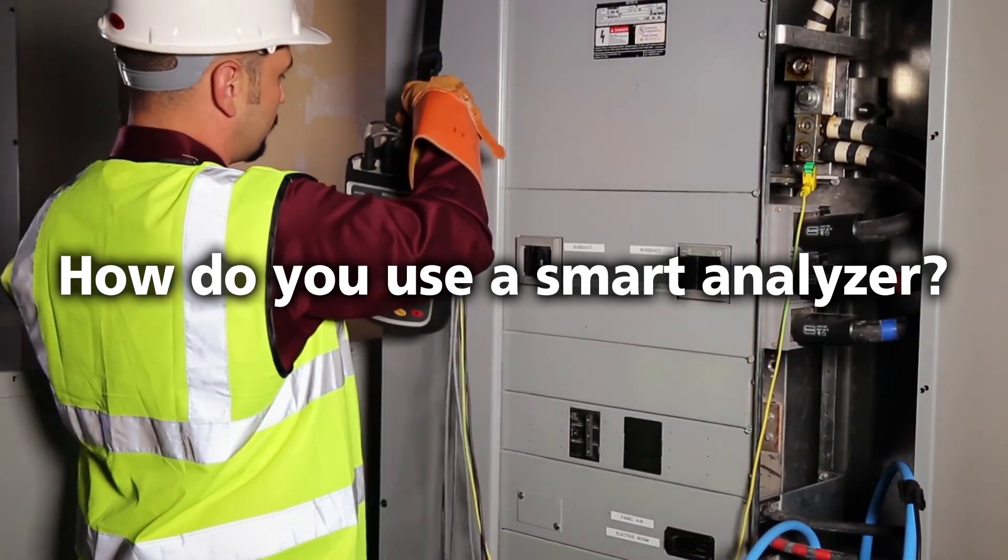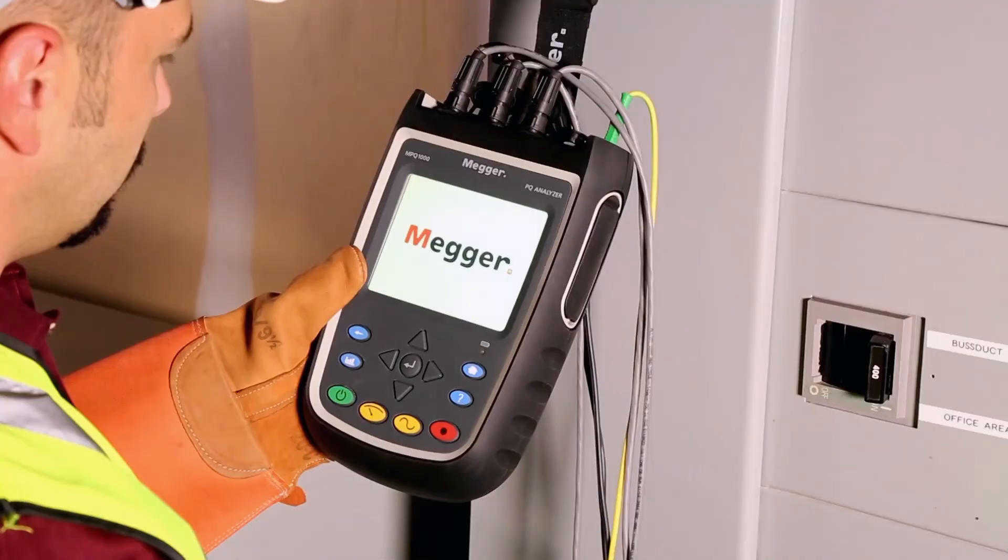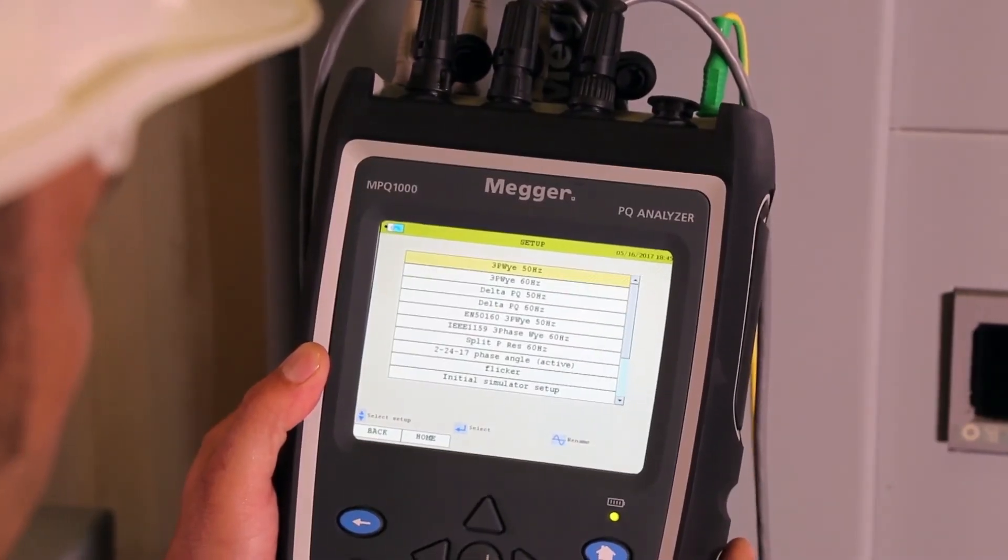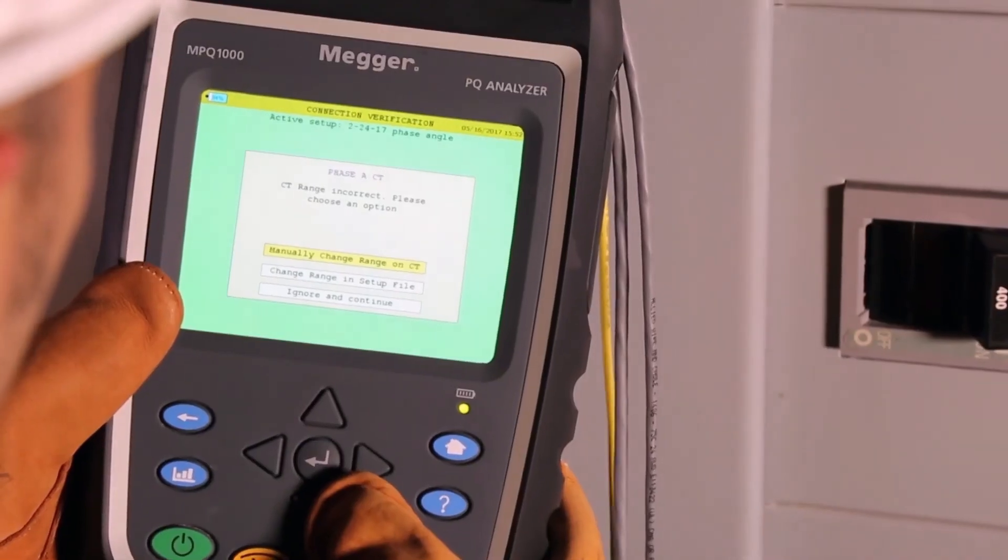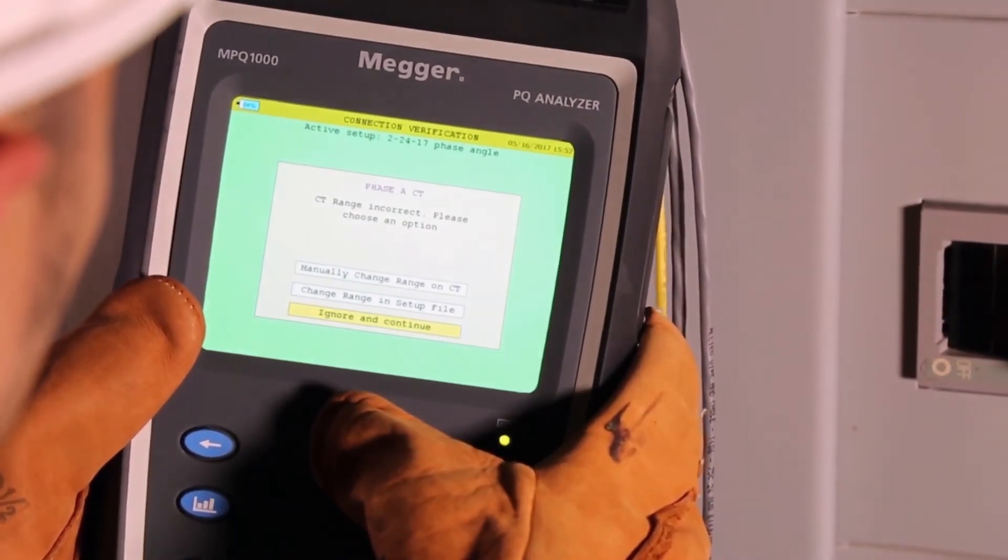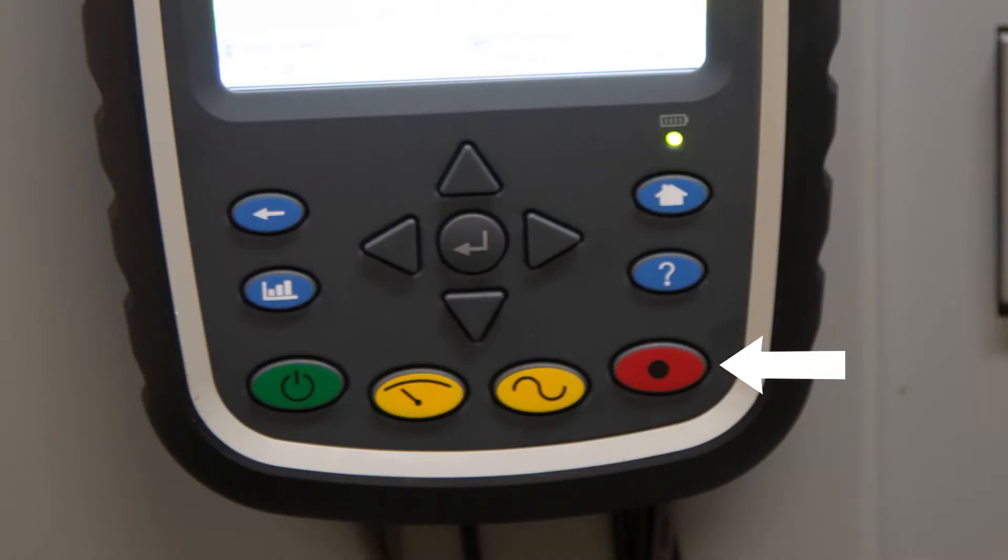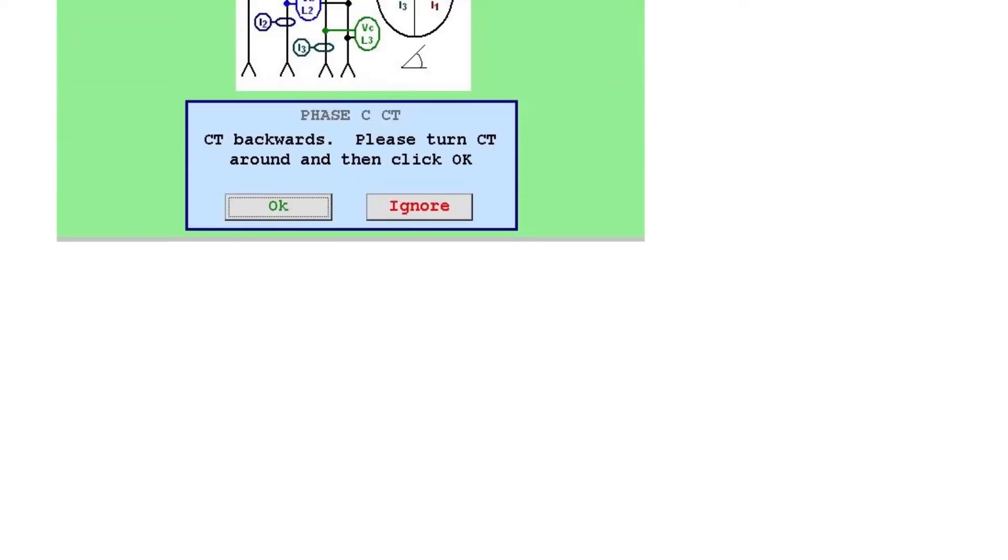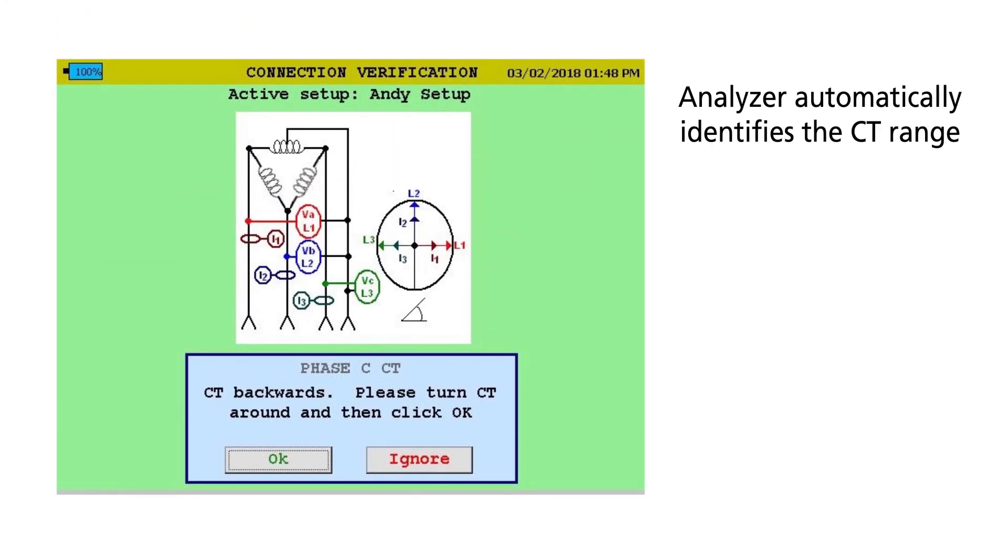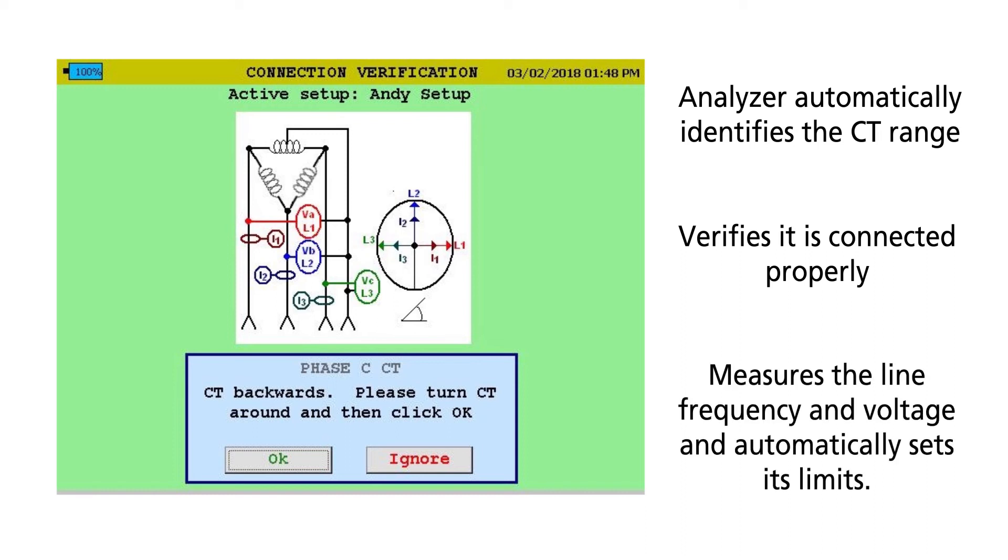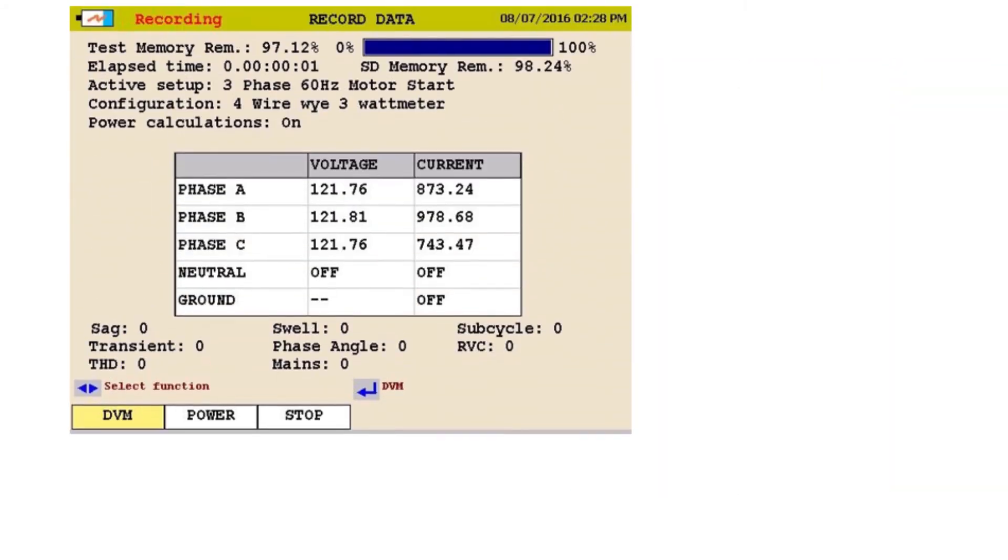So, how do you use a smart analyzer? Simply connect the analyzer, select the desired setup or configuration. There's no need to create setup files unless you want to. Set your CT range on your 4-range CT, press the button and start recording. The MPQ analyzer will automatically identify the selected range on the connected current clamps. It'll let you know if it's connected incorrectly. And the MPQ analyzer will now measure the line voltage and frequency and automatically set up all its event limits. The MPQ then starts recording.